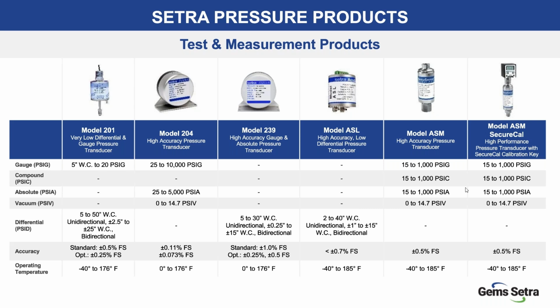The ASM products, as a complement to the ASL, support pressure ranges up to 1,000 PSI with accuracies of that. There's an error there. It should be 0.05%. Sorry about that, folks. And the same follows through on the SecureCal accessory that we're offering to be able to recalibrate the product in the field. It supports the 0.05% accuracy needs. Getting a little bit more detailed into the products themselves.